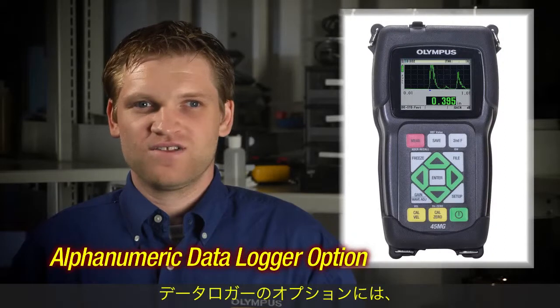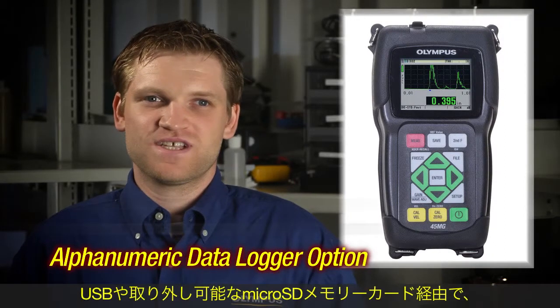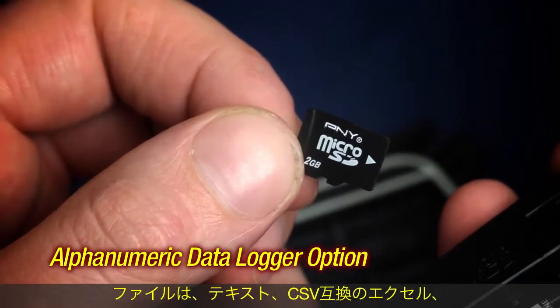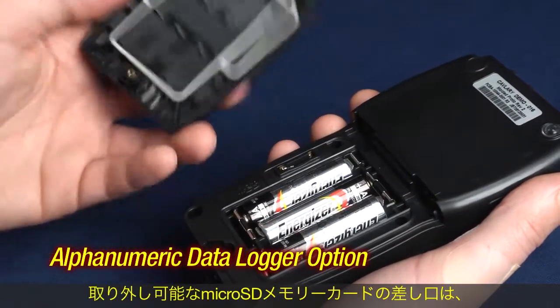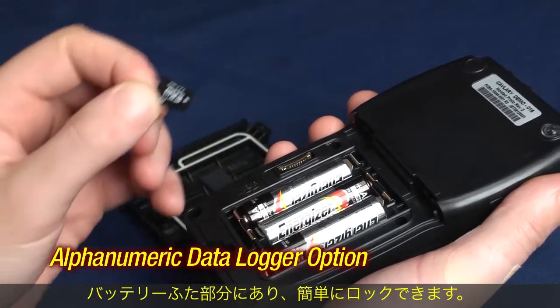The alphanumeric data logger and GageView interface program option allows the instrument to save, recall, and transfer thickness readings and waveforms via USB or the removable micro SD card. Files can be exported to the micro SD card in three formats: text, Excel compatible CSV, or as a survey file for use with GageView. The removable micro SD card is located under the quick lock battery door.